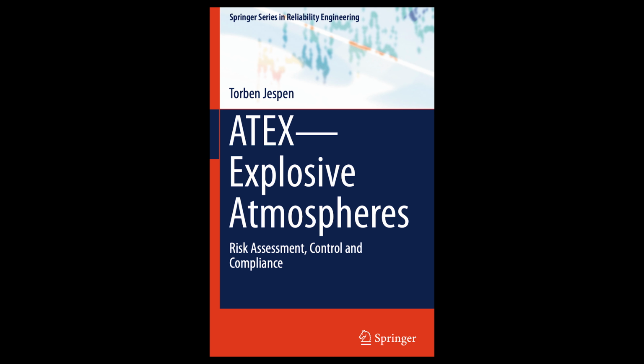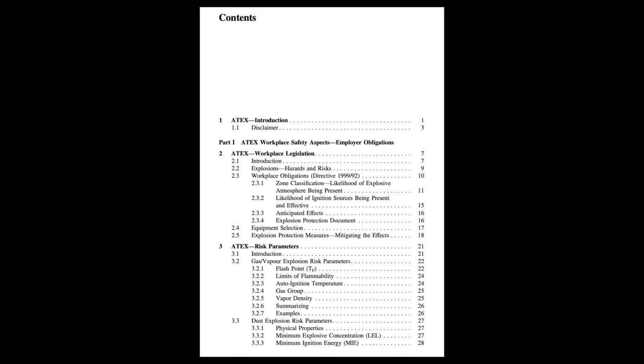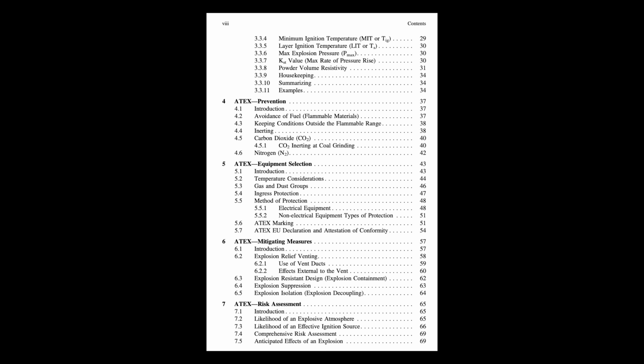Fundamentally, yes. Finally, under dust properties, the guide mentions powder volume resistivity. How does that fit in? Resistivity isn't about flammability or explosion severity, but it's key for assessing the risk of static electricity accumulation and discharge, especially for low MIE dusts. Back to static. Right, it measures how well the bulk powder conducts electricity. Highly resistive powders hold on to static charge more easily, increasing the risk of hazardous sparks. Conversely, very conductive powders allow charge to dissipate quickly if properly earthed.